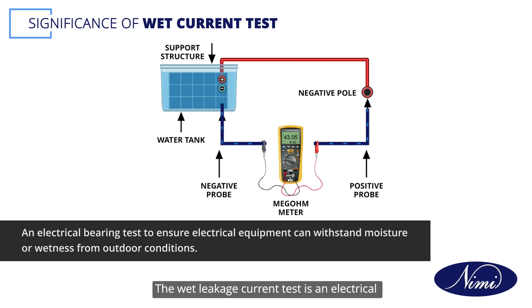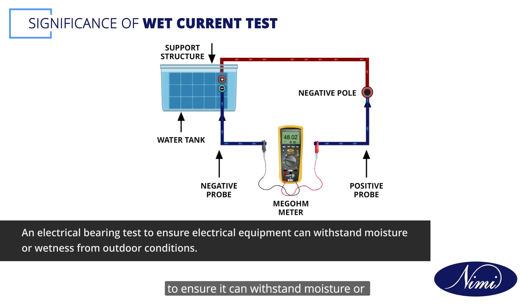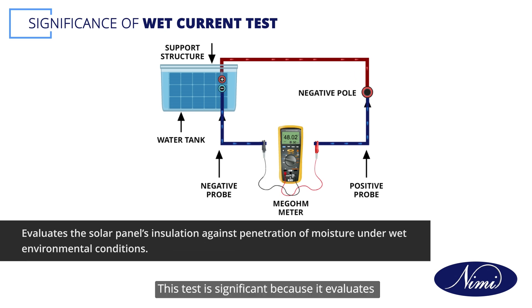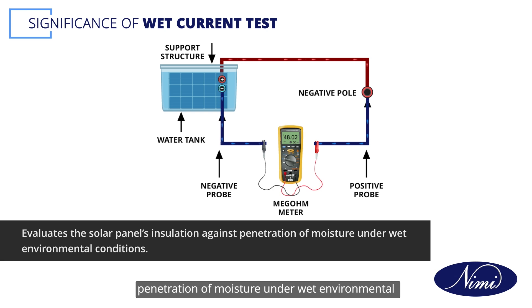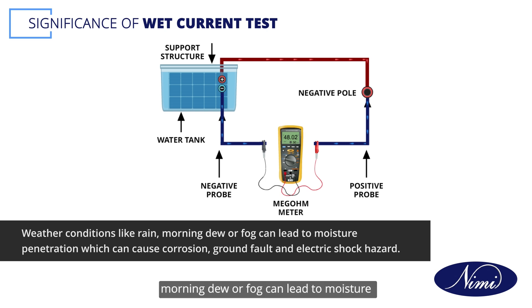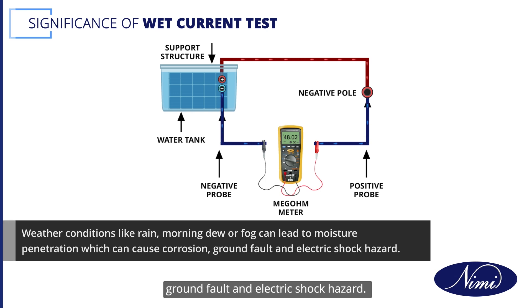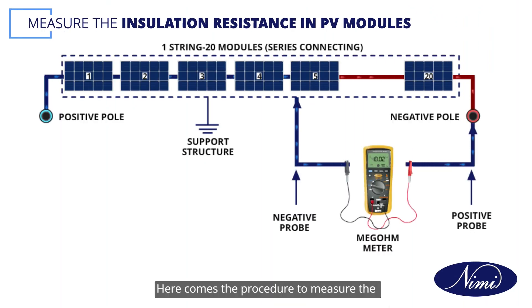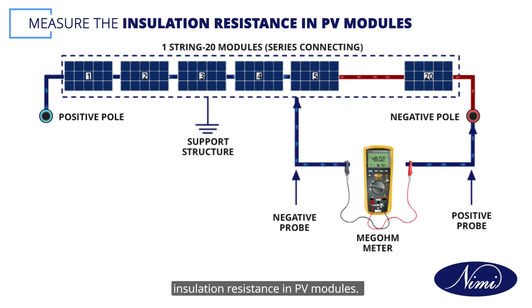The wet leakage current test is an electrical bearing test on various electrical equipment to ensure it can withstand moisture or wetness from outdoor conditions. This test is significant because it evaluates the solar panel's insulation against penetration of moisture under wet environmental conditions. Weather conditions like rain, morning dew, or fog can lead to moisture penetration, which can cause corrosion, ground fault, and electric shock hazard.